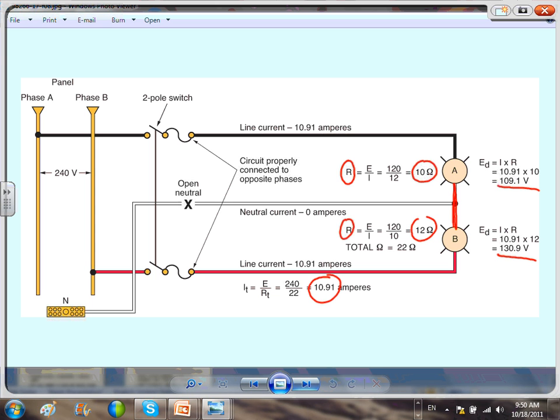If that was a motor, this will have low voltage on the motor, and this will have high voltage on the motor. These voltages are not substantial, but if it was like 80 volts and your motor is running, your motor is going to start smoking, because the motors keep pulling more current to compensate for the loss of voltage. And by doing that, they burn your equipment.